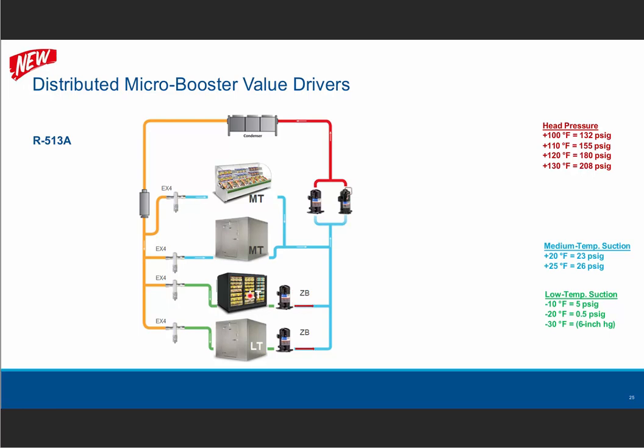So by leaving the compressor off and enabling the low temperature electronic valve, you're working that low temp case in a medium temp set point. So it's in effect a dual temp case. If something happens to that low temp compressor and it gets locked out, you can have your controls architecture assure that the electronic valve stays enabled, send an alarm, and operate at a medium temp suction temporarily until you get service there. And you can also float the head pressure and do all of the other value drivers that you could out of normal systems. But you reduce your charge, you reduce your piping, and you can use a low pressure gas for both medium and low temp.